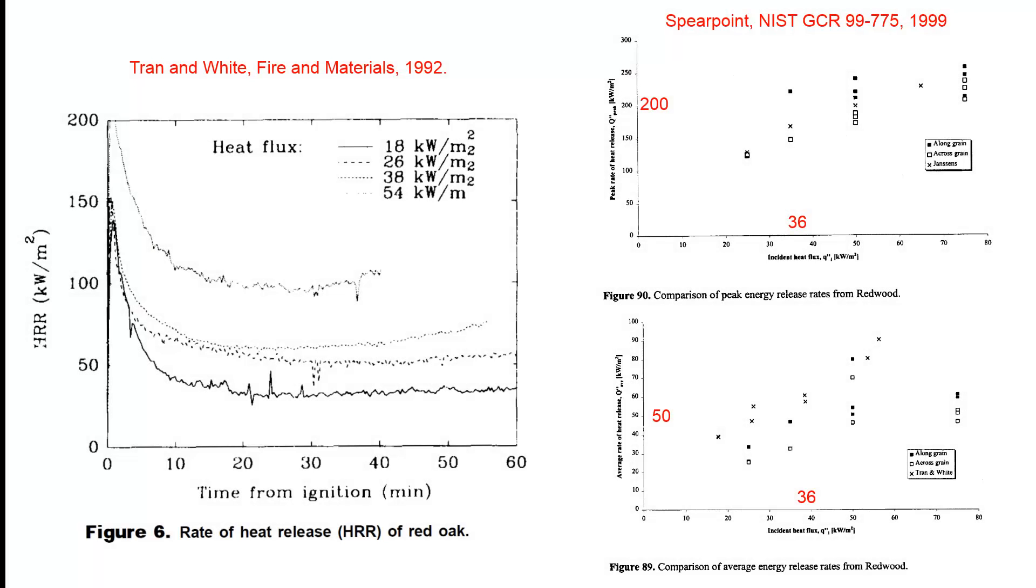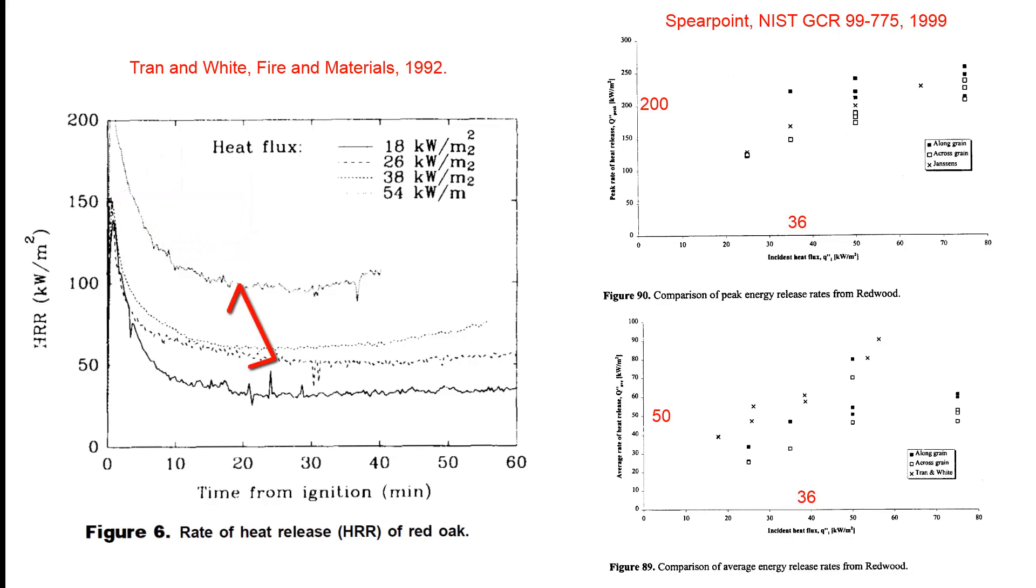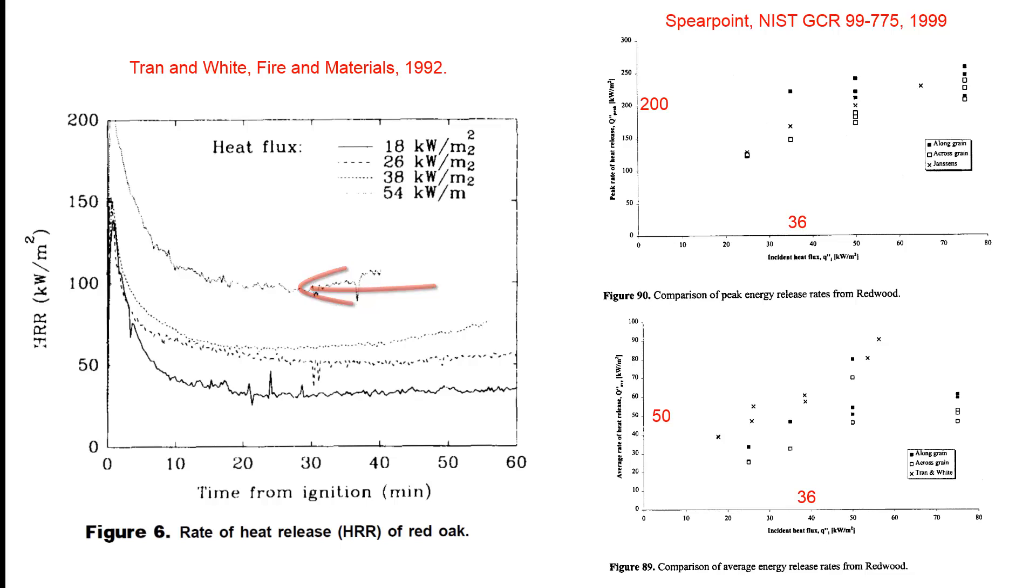Selecting the correct heat release rate is not simple. Here is some experimental calorimeter data. After ignition, a peak heat release rate occurs, followed by a decay to an approximate steady rate. However, a different heat release rate curve is obtained for different calorimeter radiant fluxes on the specimen.